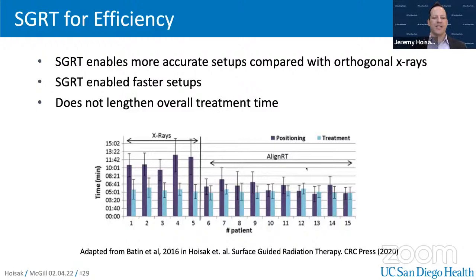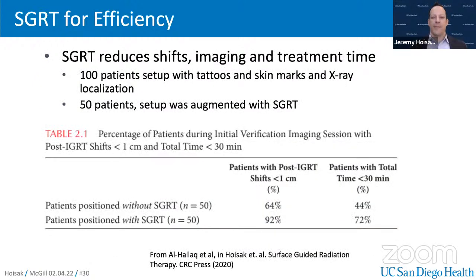So SGRT is quite a useful tool, not just for accuracy, but also for efficiency. This is internal data from Hania Al-Halak from University of Chicago. She found that SGRT reduced the required shifts to get the patient into alignment. It reduced the amount of imaging required and the total treatment time. She looked at 100 patients, 50 using tattoos and skin marks, and 50 using SGRT in addition to that. They lowered the degree of shifting required to get the patient into alignment, as well as the total treatment time. So this just shows that SGRT can really boost your efficiency.